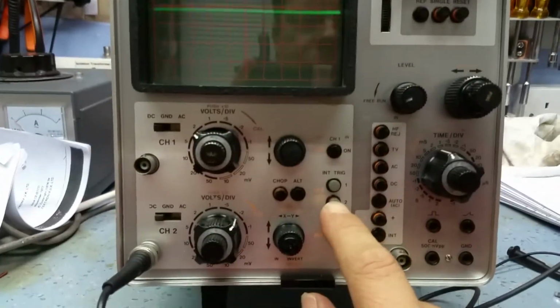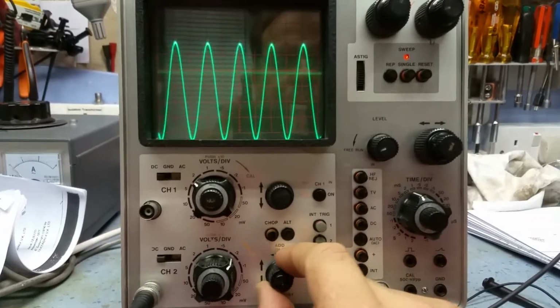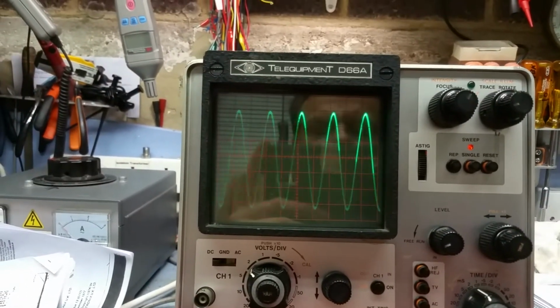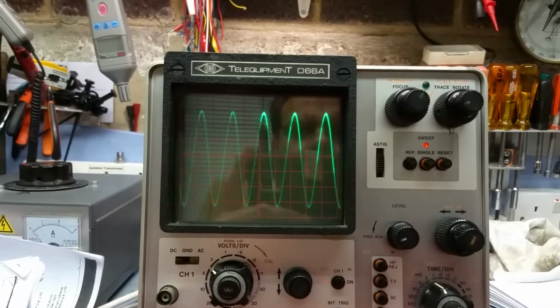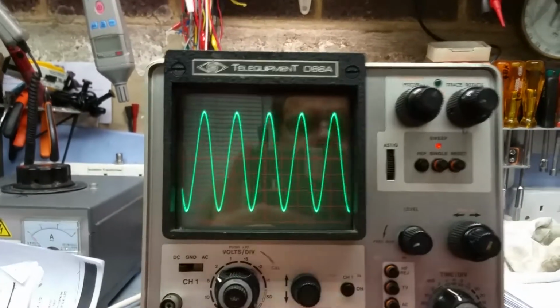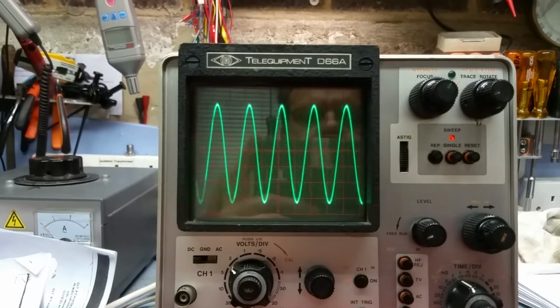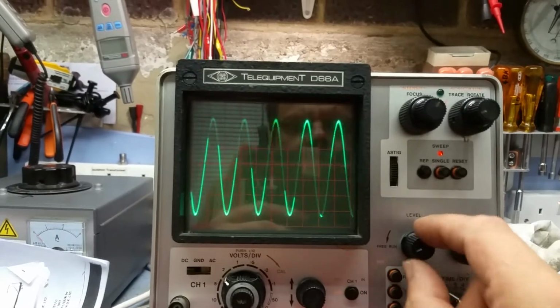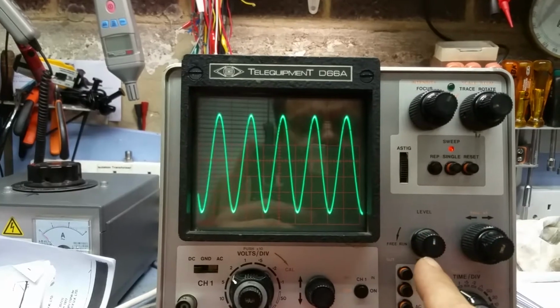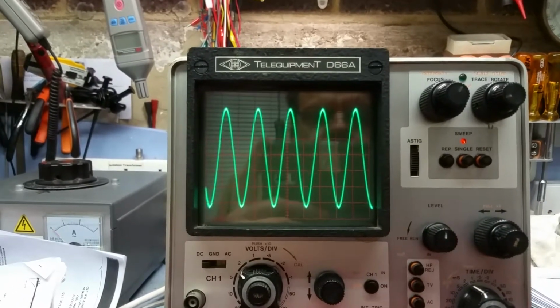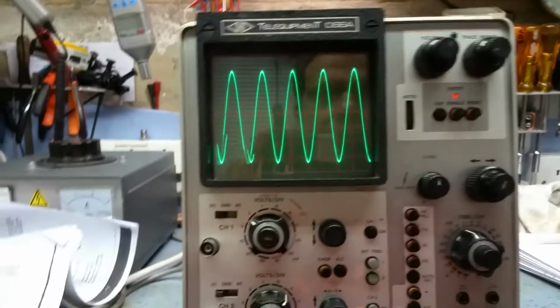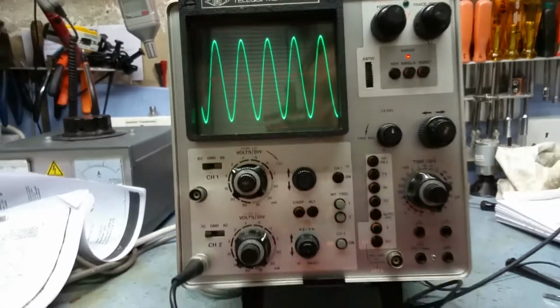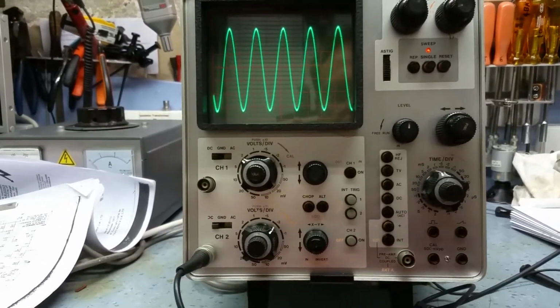But if I go back to channel 2 and set the trigger to channel 2 and bring this back, every now and then it loses its lock. It seems to be getting better actually, but every now and then it does get a bit twitchy, and you can see it's jumping around there now. So I'm not sure what that is. I don't think it's a capacitor or anything. If you just adjust the trigger stability, actually it's starting to improve. It could be just lack of use. So I'll probably have to run through a few of the calibration procedures on the triggering circuit. I've got the manual here, and it's actually quite a good manual.